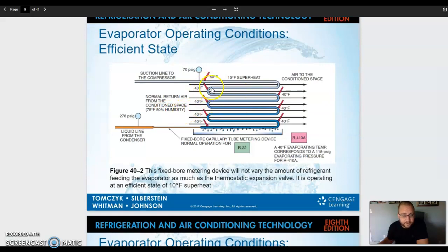Now, you also have superheat on that as well. So that 10 degrees of superheat, if you're looking at this picture here, that refrigerant's working its way through the coil, and as it goes, it's picking up heat, causing it to boil. And once it becomes 100% vapor, it reaches saturation where it can no longer evaporate. Now it is sensibly changing. So 10 degrees of superheat, hopefully we know this, is additional heat that's added to that line in addition to the saturation temp. So a system that's running at 40 degrees vapor saturation and a 10 degree superheat will have a suction line of 50 degrees.